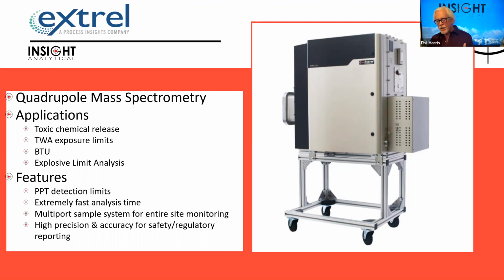We can have very low detection limits down to parts per trillion levels and extremely fast analysis time. Because of that fast analysis time, we can multi-point sample these. So we can put in valves that let us have 16 or 32 sample points and just switch between the sample points and do that fast analysis.